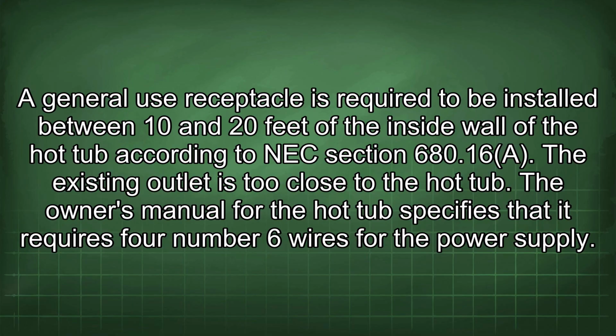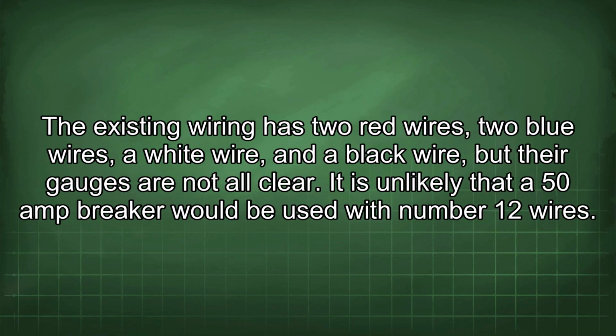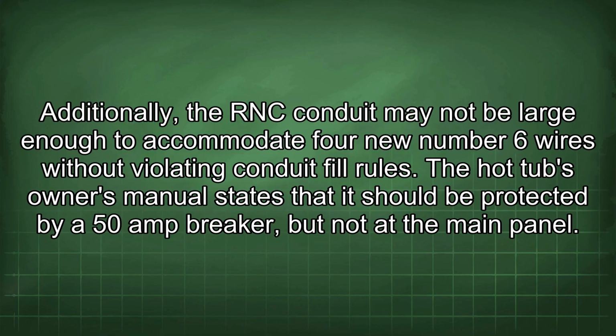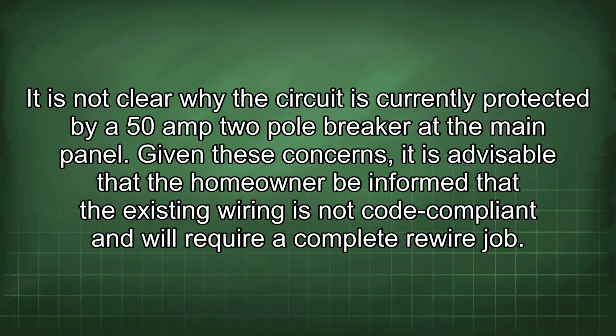The owner's manual for the hot tub specifies that it requires 4 number 6 wires for the power supply. The existing wiring has 2 red wires, 2 blue wires, a white wire, and a black wire, but the gauges are not all clear. It is unlikely that a 50 amp breaker would be used with number 12 wires. Additionally, the RNC conduit may not be large enough to accommodate 4 new number 6 wires without violating conduit fill rules. The hot tub's owner's manual states that it should be protected by a 50 amp breaker, but not at the main panel. It is not clear why the circuit is currently protected by a 50 amp 2-pole breaker at the main panel.